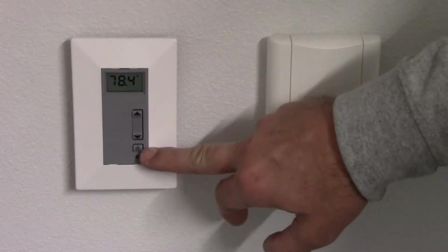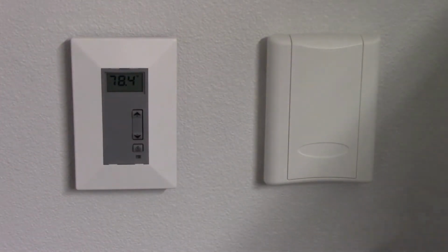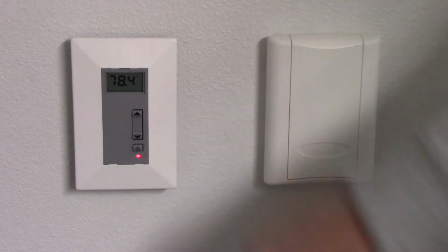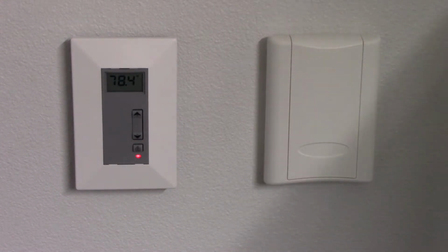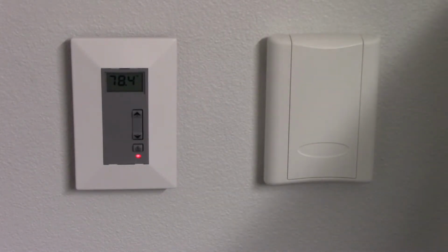This is the override button. So if somebody comes in when the building schedule is off, it'll give them the ability to hit this button. You'll get a red light that says you've got a local override on, and it'll override the unit for a preset time, typically 60 minutes, and then it'll turn it off. It won't occupy the whole building, it'll just occupy the unit that's serving this room.